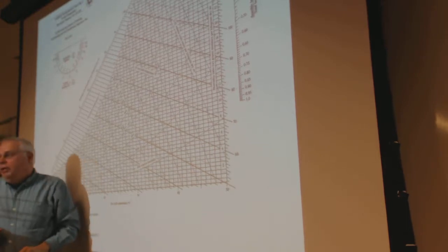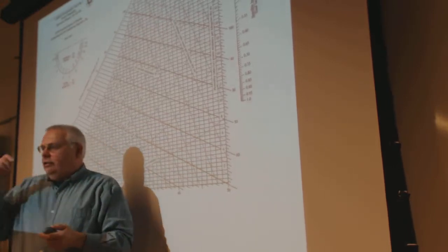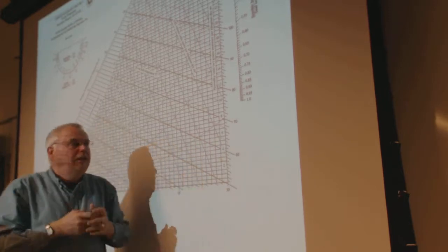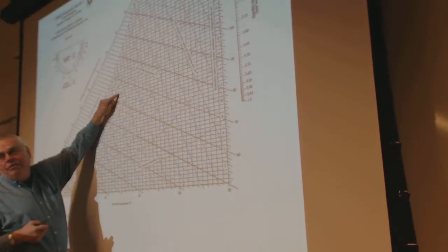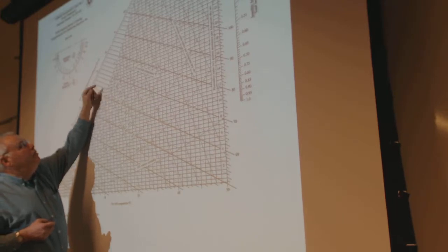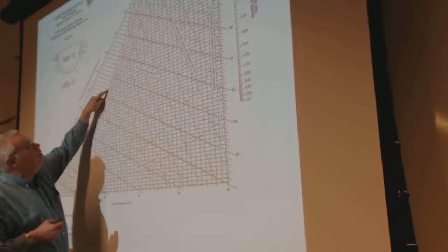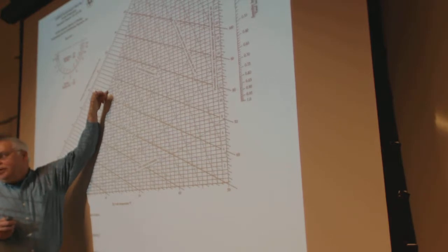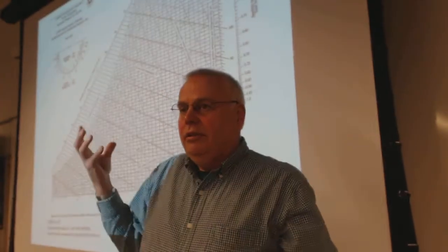And now to find the wet bulb, that would be to take the same enthalpy and force it to saturation, so we're going to, that's swinging the washcloth around. In its vicinity, it's 100% relative humidity, and it'll go down to that, it's kind of harder to explain, but basically, you take this point, and take, it's with the same enthalpy, we're not adding energy, we're not taking it away, but as it vaporizes water, it's driving down the temperature to, it's a constant enthalpy value, and it's going to be, let's see, it's going to be 75, over here, and 20, 21, it's like a 21 and a half degrees or something, it's not 20 degrees, it's not 25, it's like 21 and a half would be the temperature, if you just swung something around that was wet, that would be the temperature it goes to.